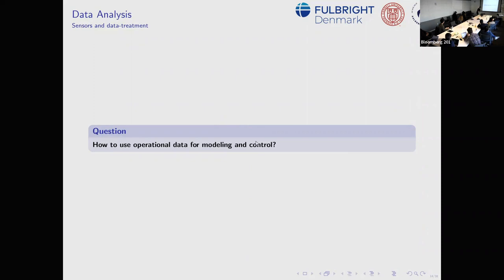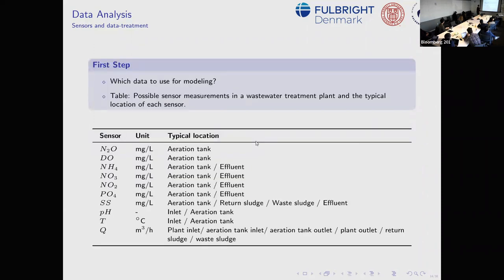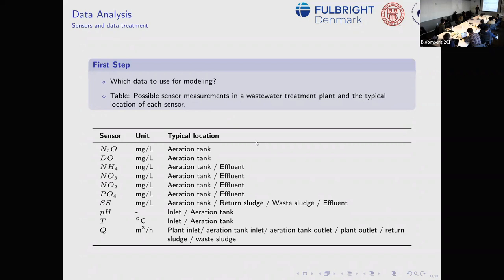The first step is deciding which data to use. There's a typical location problem: many systems are very different, and sensors are positioned at the effluent because that's what they're checked for, not inside the process itself. You're controlling a tank of enormous size with bacterial colonies that may be changing in different areas and different activities, and you measure maybe one place in this huge vat — approximating and controlling something you don't exactly know.